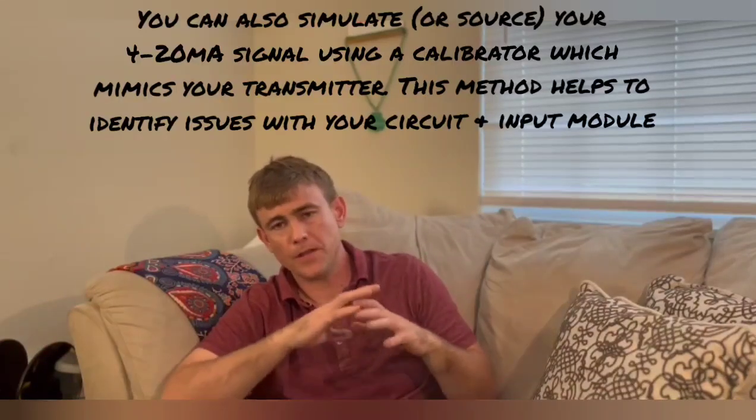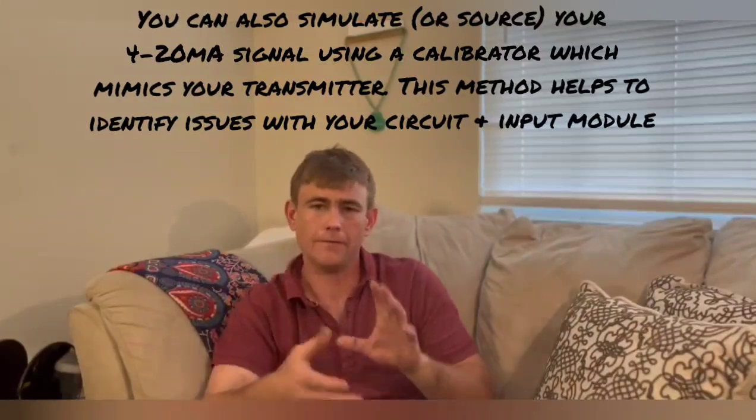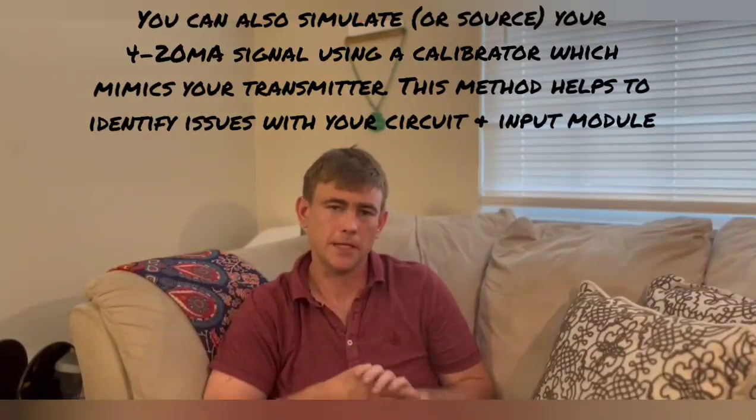check your transmitter, you check your readings, you can calibrate different parts of the system. Maybe you're just doing the loop check to verify the 4 to 20 milliamps coming out based off those standardized pressures that you have attached to your sensor. Maybe you're checking the whole process. So you apply the real pressure, and then you go back to the control room and you look on the SCADA screen, and you can do your calibration that way. And that's all going to be set up when you show up. You just have to follow the procedure and pay attention to detail.